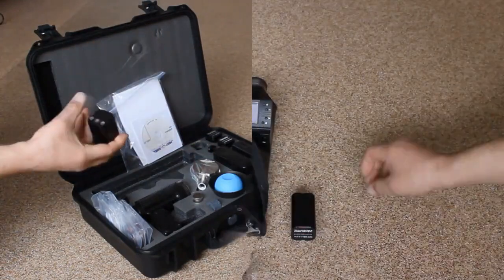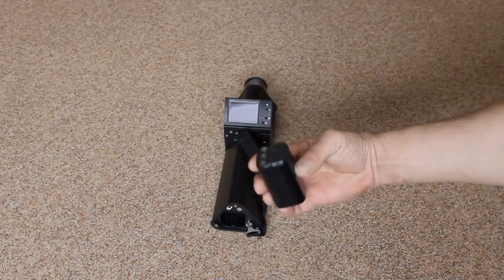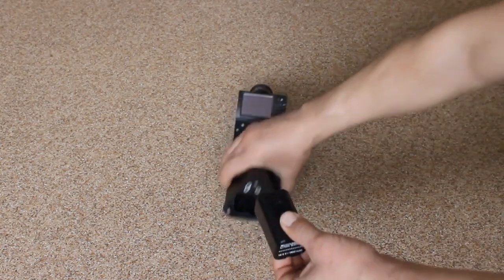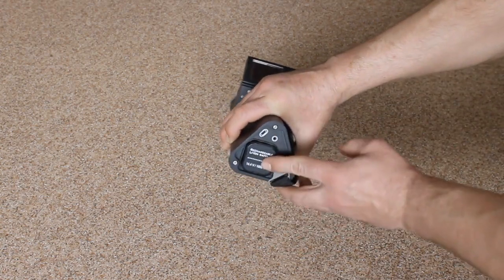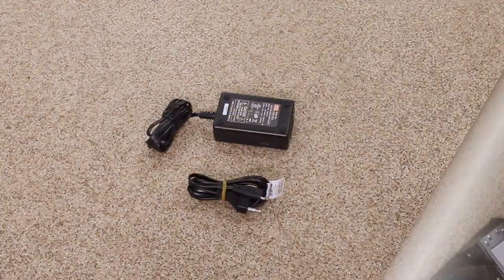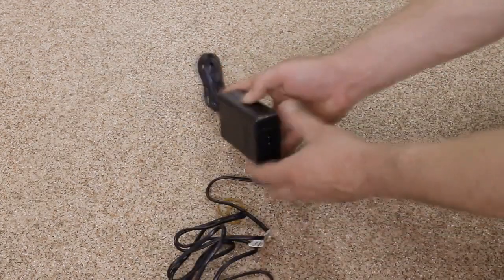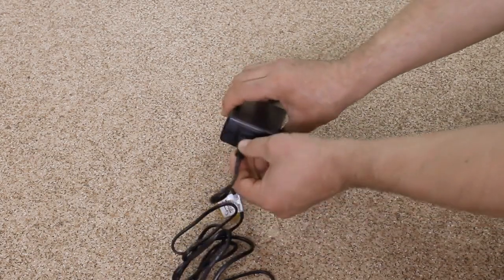Three lithium-ion batteries are included in the complete set. Each battery provides up to four hours of continuous work in vapor detection mode and up to two hours of continuous work in particle detection mode with the TWIN. Instead of the battery, one can take the power adapter out of the case, then plug it into the detector and into the AC main.